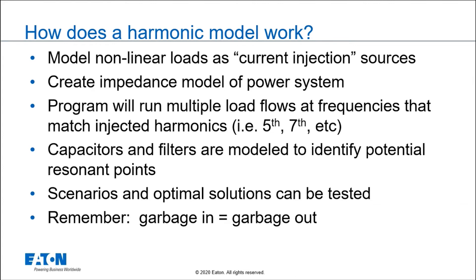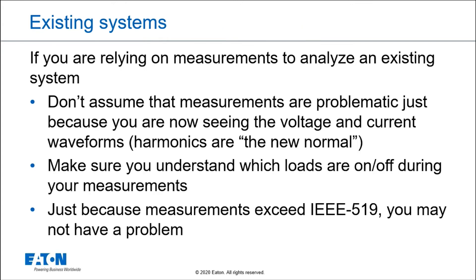Capacitors and filters are modeled to identify resonant points. Then we look at scenarios to check for optimal solutions — do we put a harmonic filter in, do we use phase shifting transformers? But remember, garbage in equals garbage out in a model. So if we don't have a good model, we can't rely on it to give us a good solution.